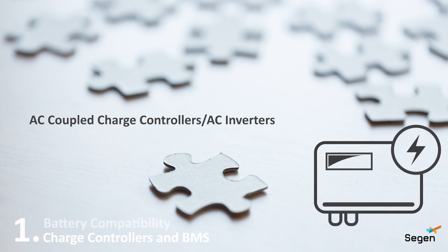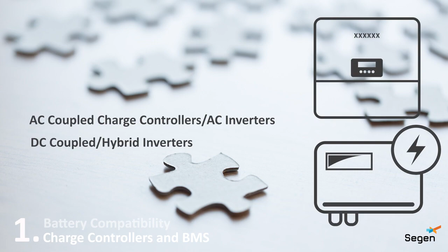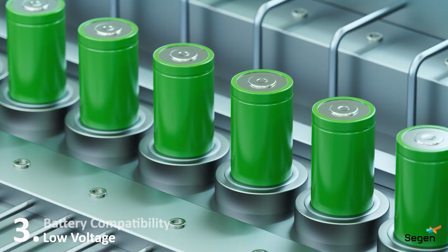Whether using AC coupled charge controllers, AC inverters, or DC-coupled hybrid inverters, it's important to ensure the battery packs chosen are compatible with the charge controllers. Battery solutions can run at low voltage or high voltage, and manufacturers test and approve their battery chargers with different battery packs to ensure compatibility. Using non-compatible products can be dangerous, invalidate warranties, and be costly to replace.